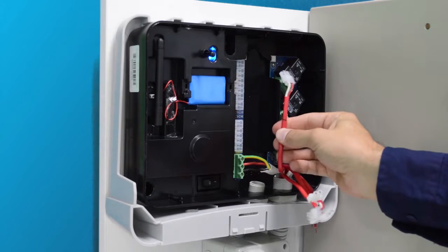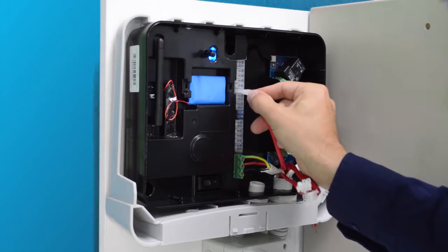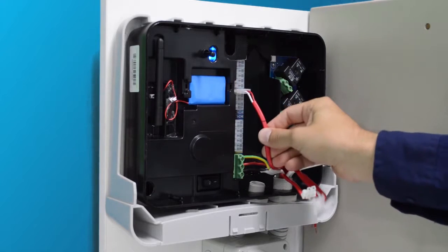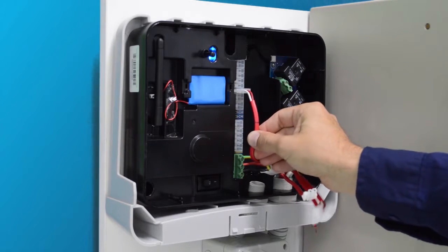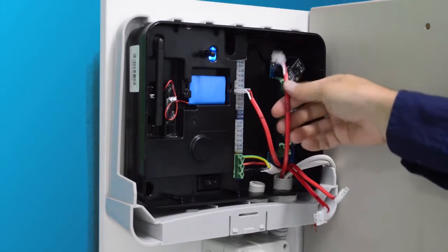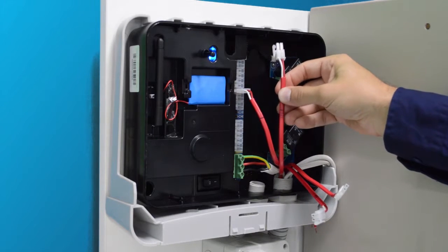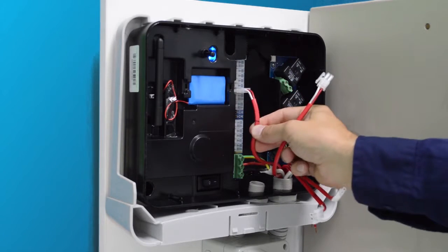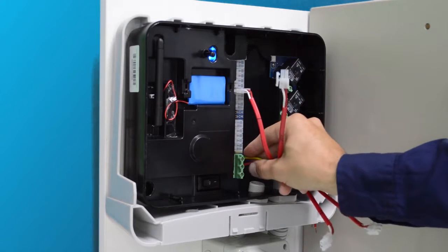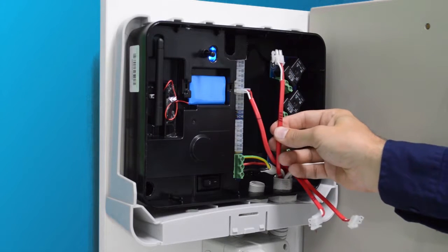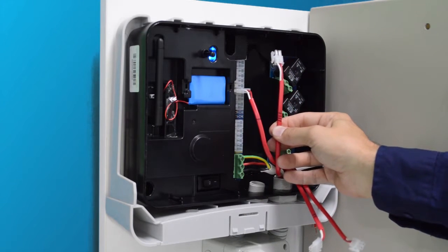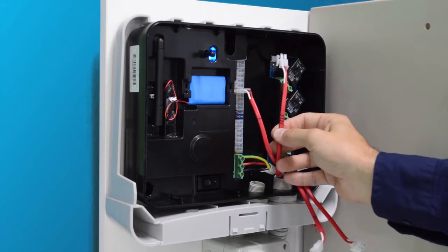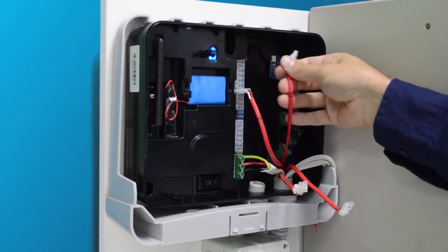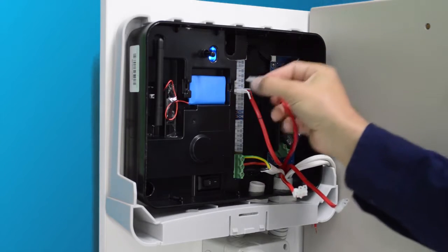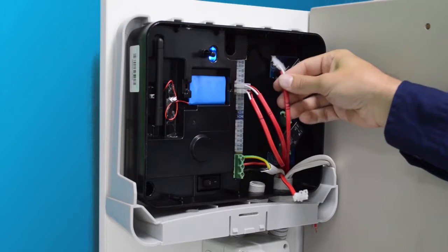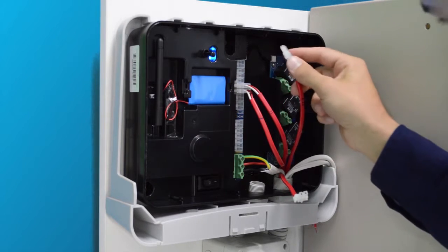Plug the first current clamp labelled 1 into the port labelled phase 1. It is important that this phase is the same phase as you have clamped current clamp 4, the solar clamp, around. For example, if you have clamped this around white phase and powered the unit from the white phase, you must have selected a white phase for the solar current clamp to clamp around on the solar mains active. Plug current clamp labelled 2 into the port labelled phase 2. Plug the current clamp labelled 3 into the port labelled phase 3.